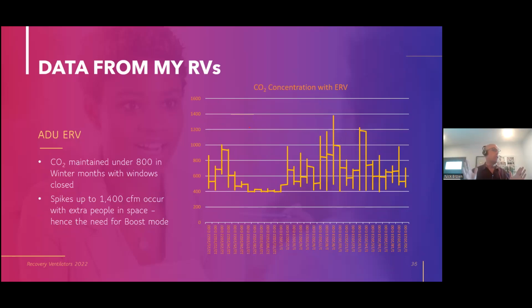How about indoor air quality? That's one of the main reasons we're doing this, right? Well, here's the ERV. I monitored the ADU's indoor air quality. I asked them to leave the monitor plugged in. And this is a period, December 2022 to January 2023, so about a month. You can see most of the time we're maintaining CO2 concentrations under 800 parts per million, which I would argue is a really good target to have.